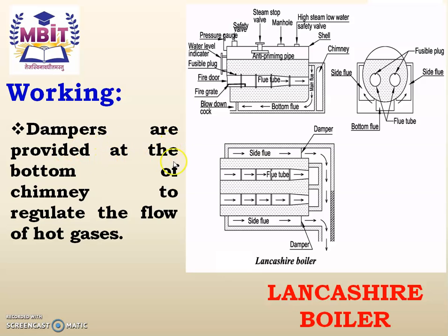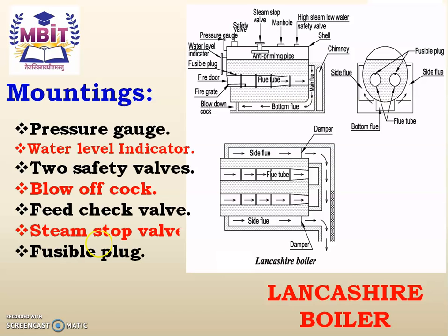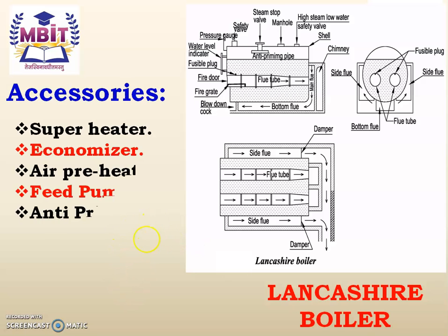Dampers are provided at the bottom of the chimney to regulate the flow of hot gases. The different mountings attached to this boiler are: pressure gauge, water level indicator, two safety valves, blow-off cock, feed check valve, steam stop valve, and fusible plug. The accessories that can be attached to the Lancashire boiler are: superheater, economizer, air preheater, feed pump, and anti-priming pipe.